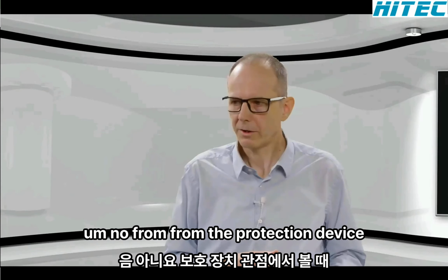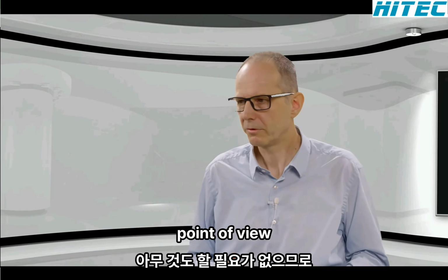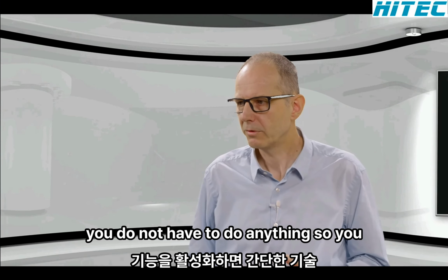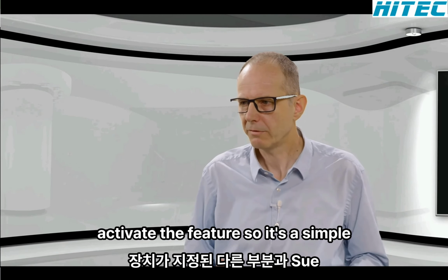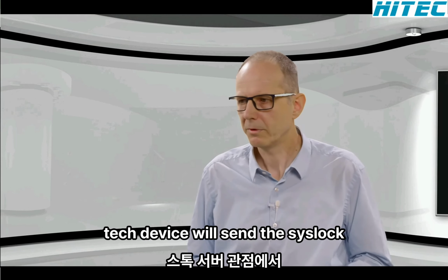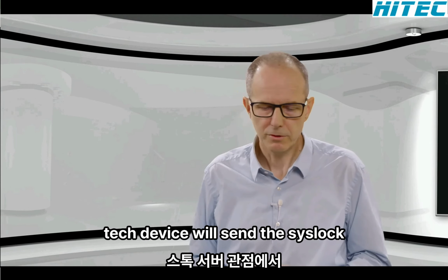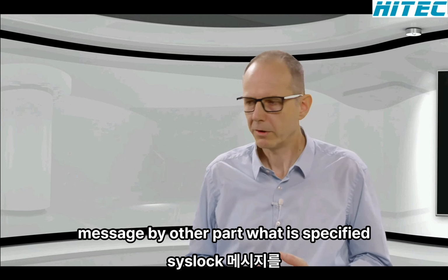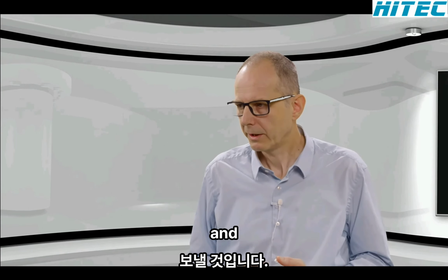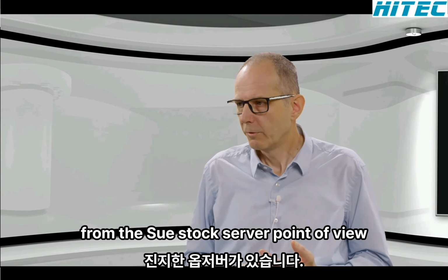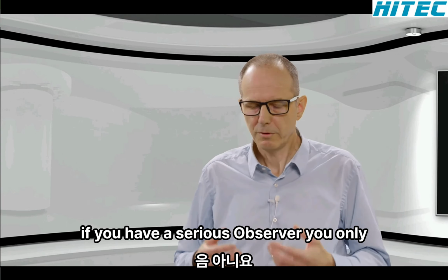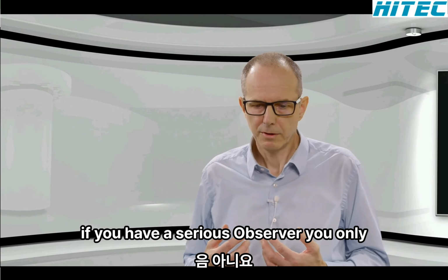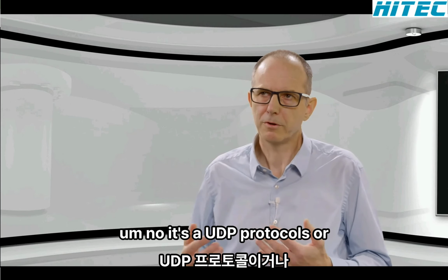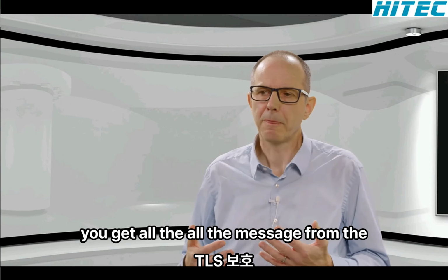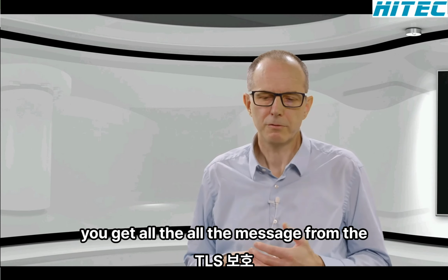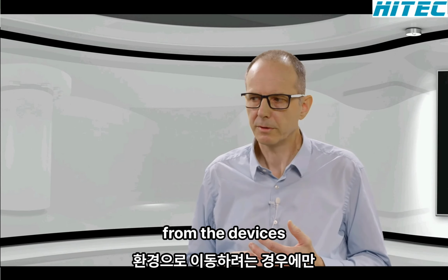From the protection device point of view, you do not have to do anything, you just activate the feature. The SIPROTEC device will send the syslog message via the specified port. From the syslog server point of view, if you have a syslog server, it's a UDP protocol, so you get all the messages from the devices.